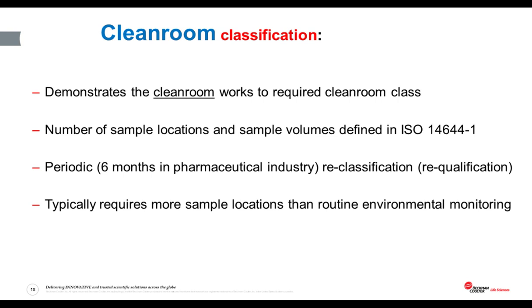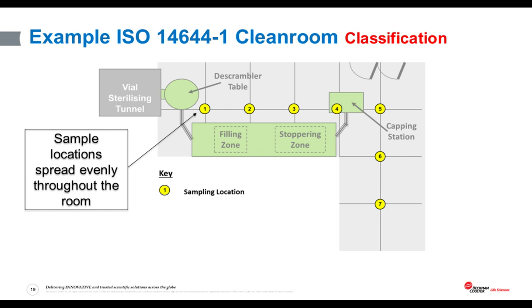The user themselves must take ownership of the decision of where environmental monitoring is done routinely. It must be based on a risk assessment of their specific production process, their product, and the clean room itself. Clean room classification focuses on the clean room itself — we're not looking at risk to the product, just checking that the clean room is performing to the target cleanliness class. It is very well described in ISO 14644-1 and is typically carried out every six or twelve months depending on your standard operating procedure.